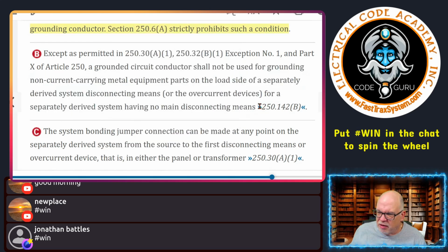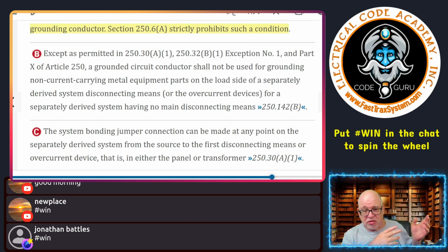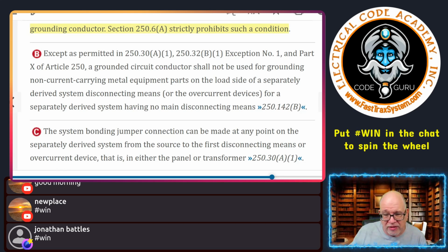All right, so remember where I said you could use the grounded conductor in 250.142A to bond metal parts on the supply side? You're prohibited from doing anything like that except in 250.30A1, 250.32B1, exception 1. And you remember that's the old rule where you had a detached structure and you could use a neutral conductor to do that, but that was like 1995. It was a long time ago. Not anymore. Now you have to separate grounds and neutrals at a remote distribution panel. But years ago, it was an allowed practice under the exception, okay?